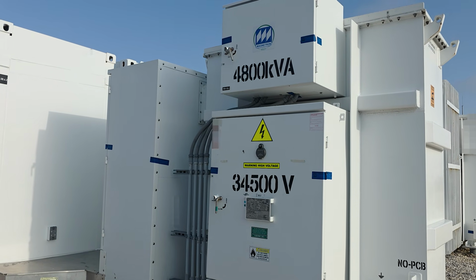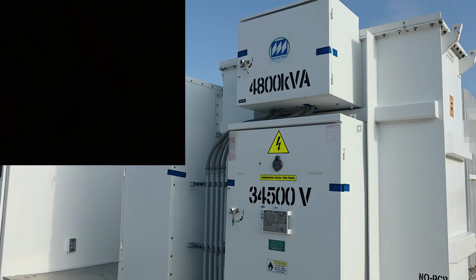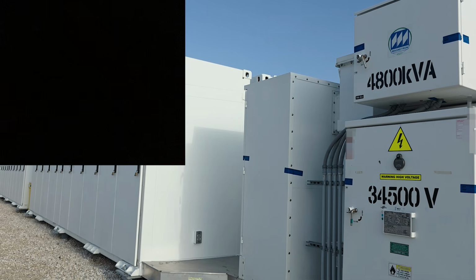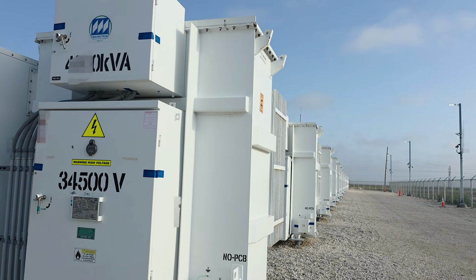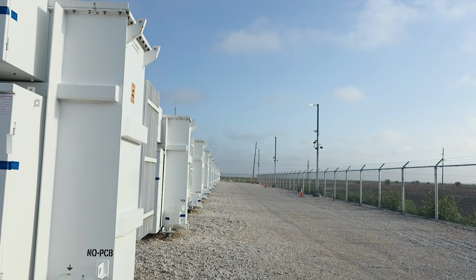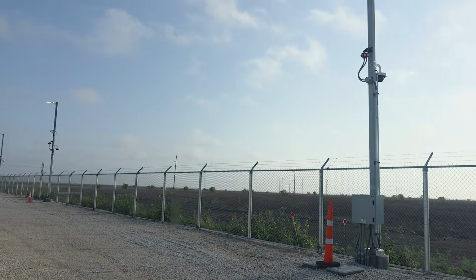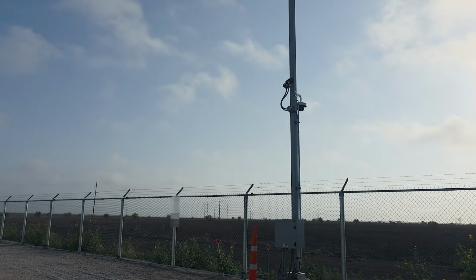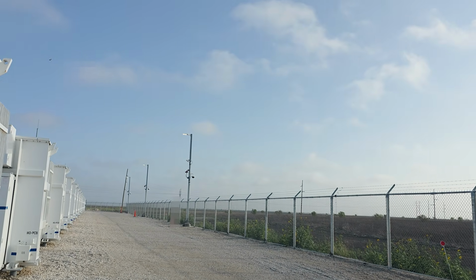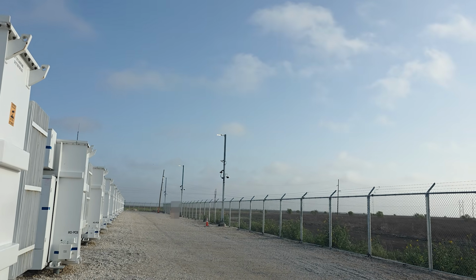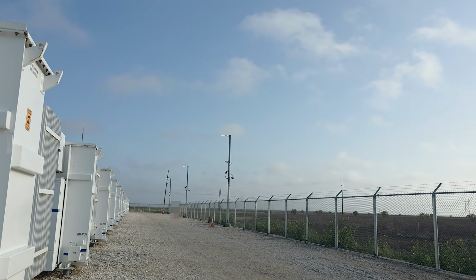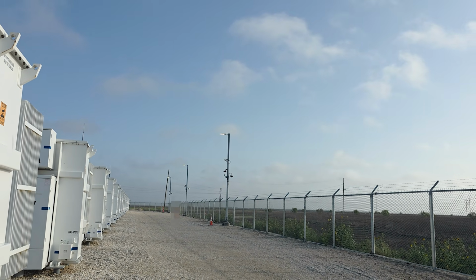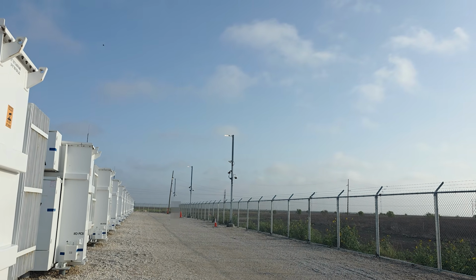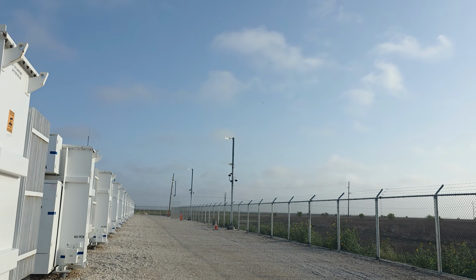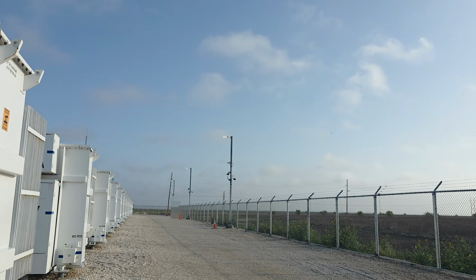But if there's a problem with the batteries themselves, they will burn up. They will burn up the entire skid. They will burn up other skids around them. So how do you not only prevent that, but how do you know if that's happening? Well, you've got these sensors on all these fences. And on these sensors, there are cameras and there are thermal cameras. They're not cameras like FLIR, where you see the cop helicopter looking down at people with a thermal camera. It is that, but it's not really viewable. And let me explain that.